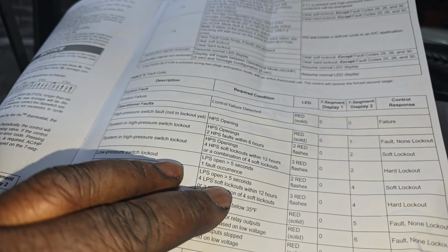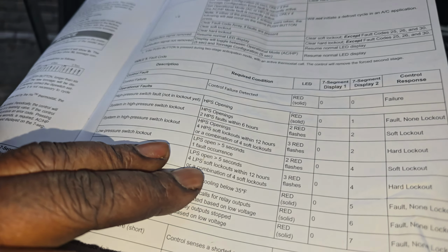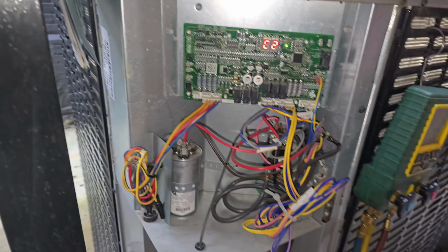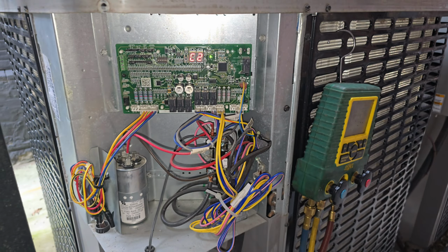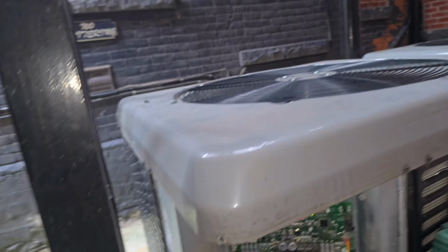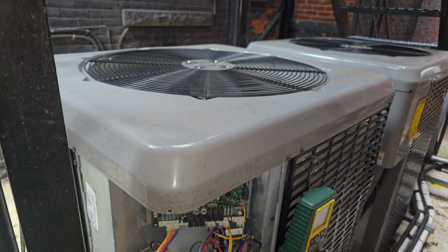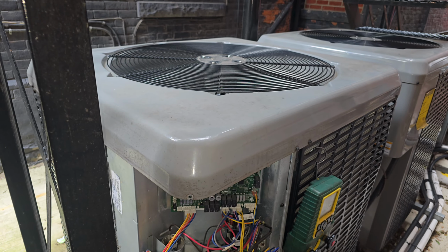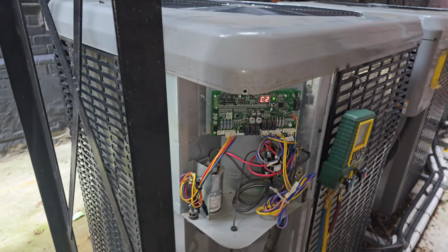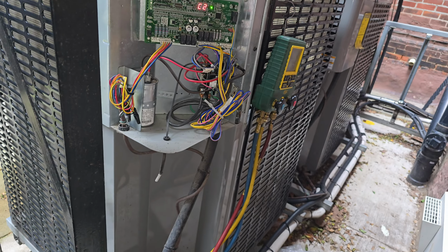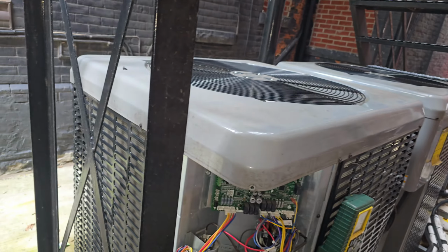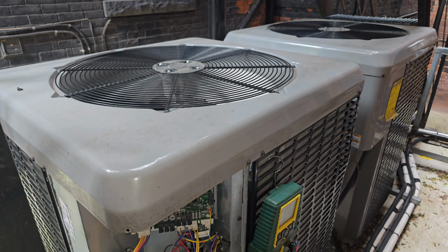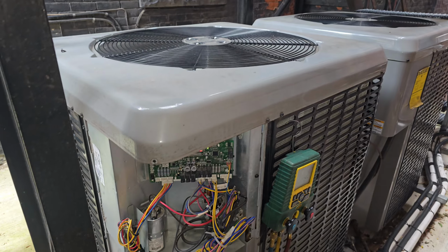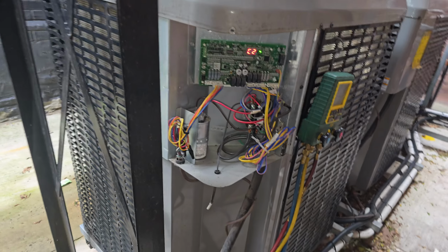It's a lockout because the condition could be low pressure open for 5 seconds, or low pressure soft lockout within 12 hours. So that just signifies the system is low on freon. If this system continues running this way, on a normal day, when the temperature heats up to like 25 degrees on the outdoor, or even over 25 up to 30 Celsius, this unit is going to really work hard, and this unit will trip off on low pressure. So to bring it up, we will need to find the leak and then recharge it fully. That should bring this unit back up properly.